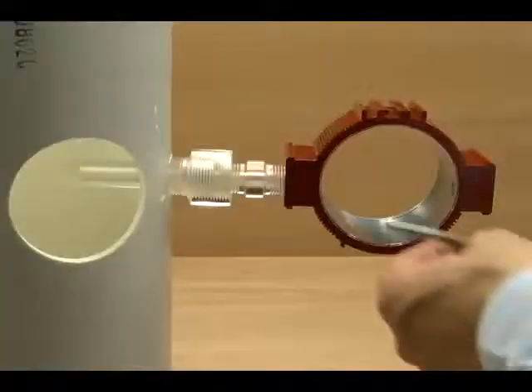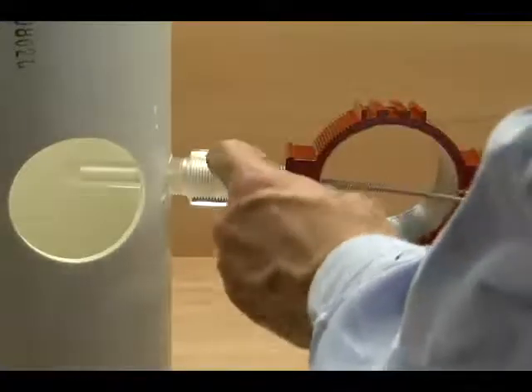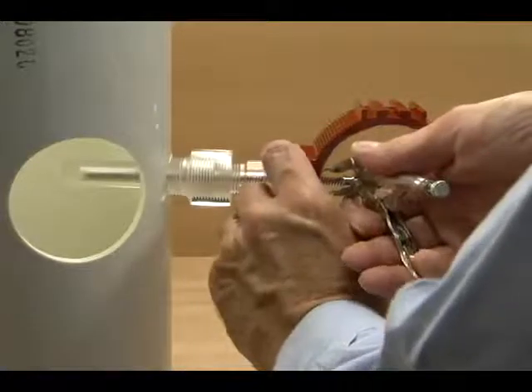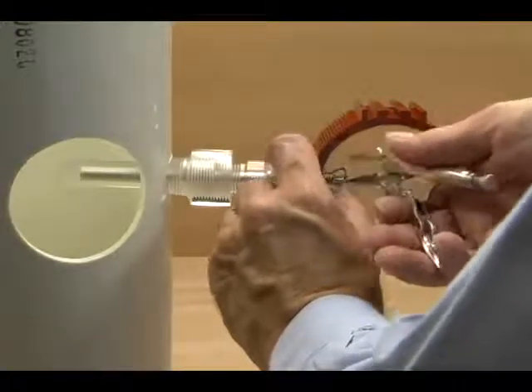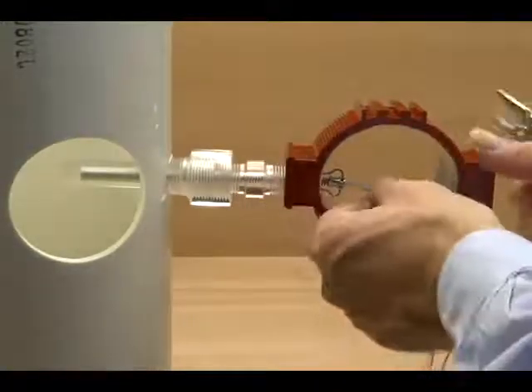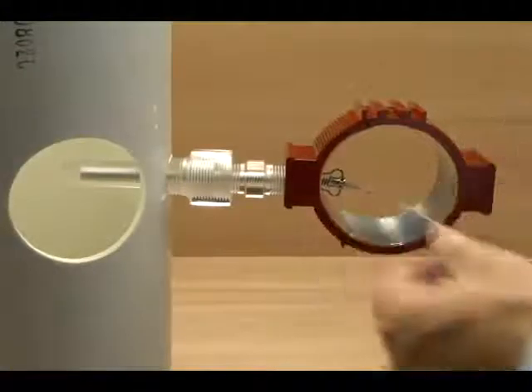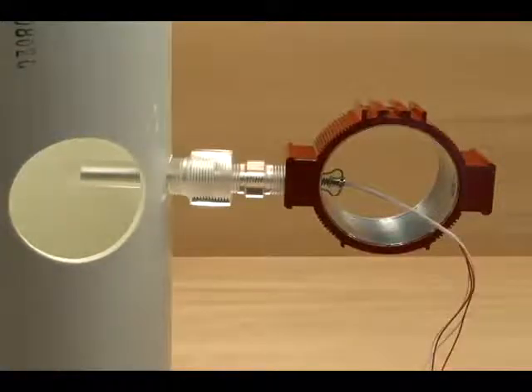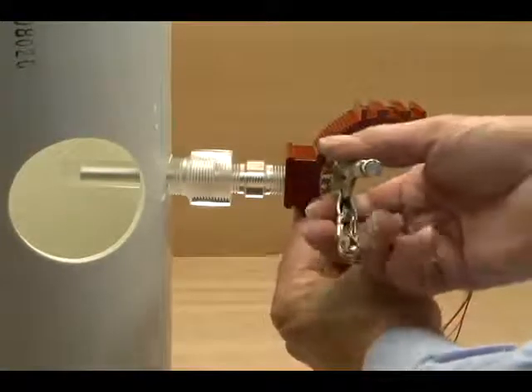Now, when you reinsert the probe, use a pair of pliers to squeeze the prongs together and hook them into the transmitter opening. This will put pressure on the probe spring that will drive the tip all the way to the end of the thermal well. To remove the probe, just squeeze on the spring and pull it out.